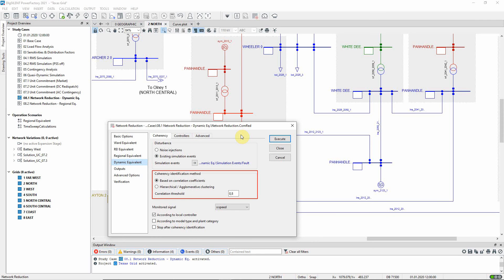The coherency identification method is selected, and in this case it is based on correlation coefficients, with the default threshold of 0.8 being specified. This is a good starting point. With a lower value, fewer equivalent generators would be created, but the accuracy could be compromised.